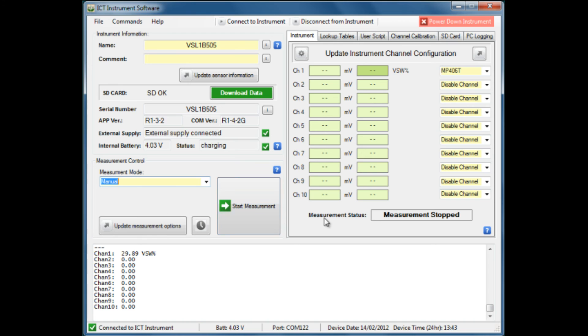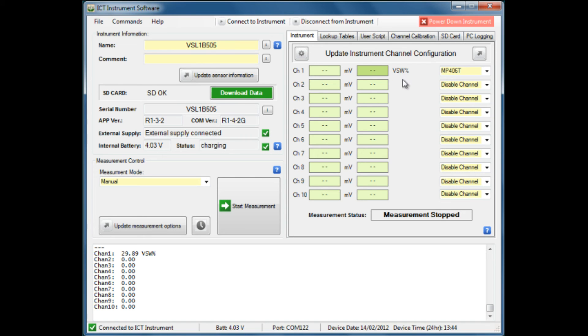We're ready to go ahead and start the calibration, and we notice that on channel 1, the channel we intend to use, the measurement results window is a different color—a darker shade of green that indicates we actually already have a calibration done on channel 1. However, we don't wish to use that calibration, so we will do a new calibration.